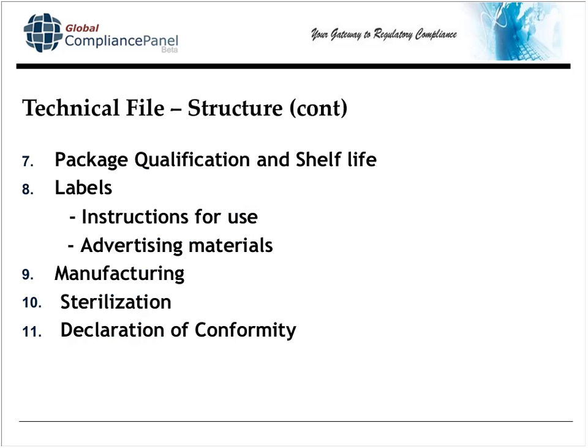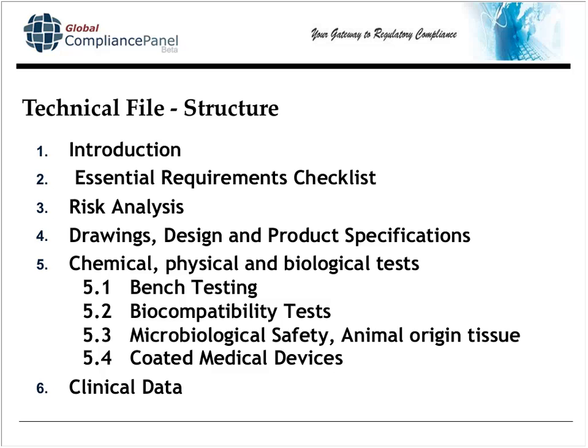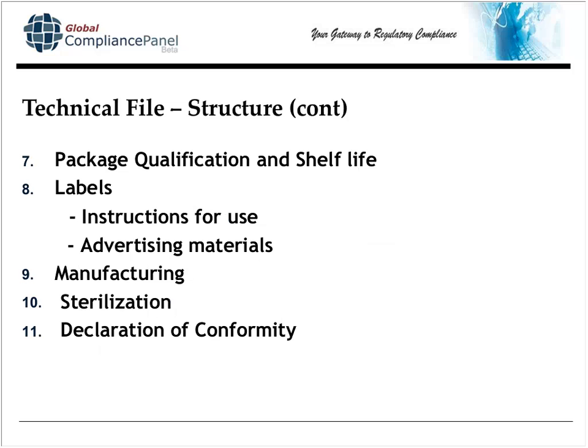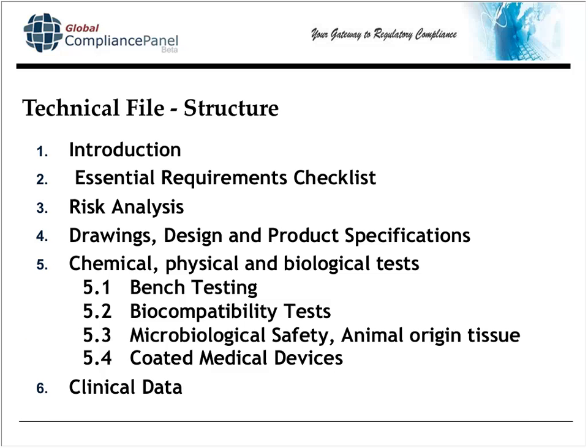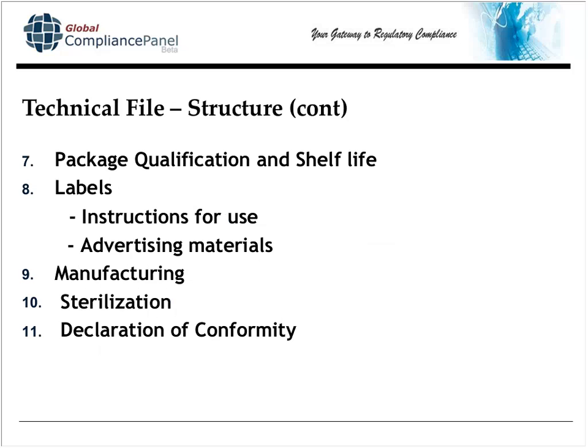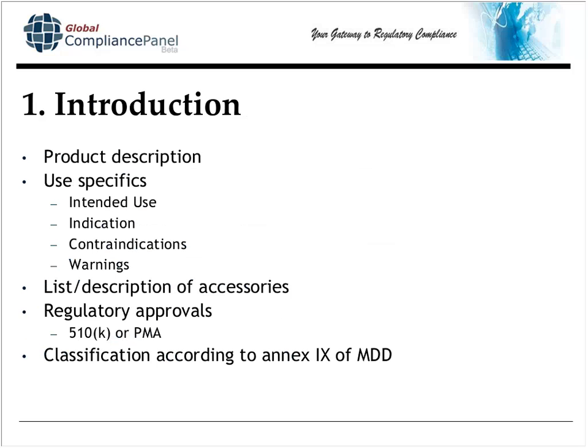There are quite a few sections. If you have no clinical data in your technical file, don't just leave that item empty — put a section in there for clinical data and explain why it is not required. Section 7 is package qualification and shelf life. Section 8 is labels, all of your instructions for use, but also your advertising materials are part of your technical file. Section 9 is manufacturing and sterilization, and the declaration of conformity is the last section.